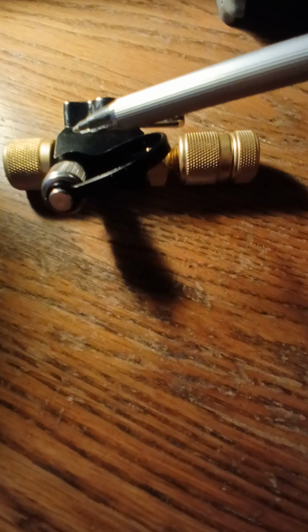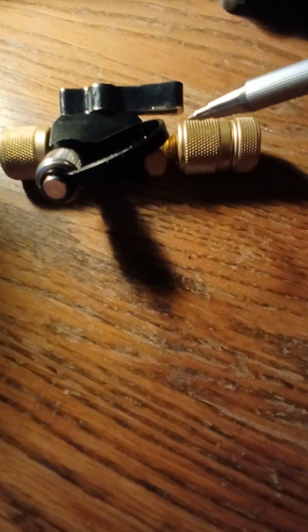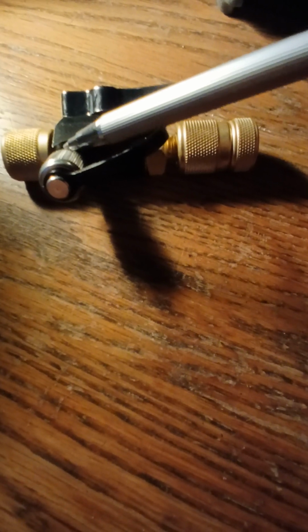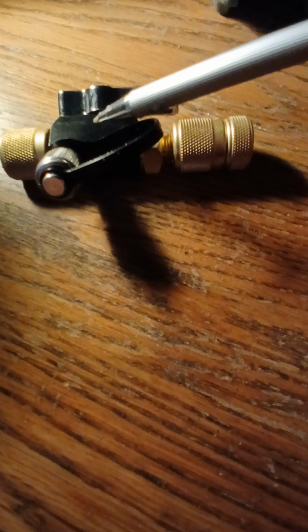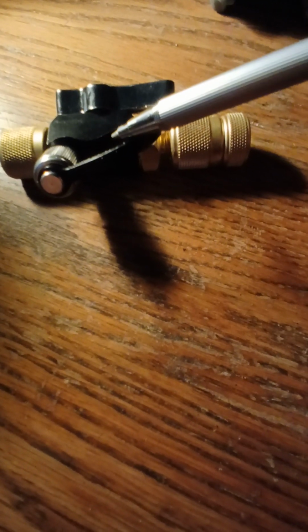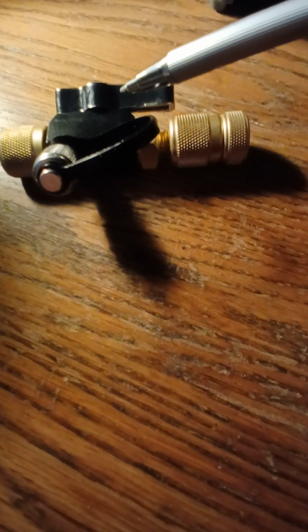My opinion is, and I hope I'm not wrong here, and again, the experts can add to this, that if you have this cutoff, you still need to build pressure so you could test your pressure here, or in a case where you were pulling a vacuum. So I'm thinking perhaps one reason that this is located in the front as opposed to on the back side is that if you cut it off on the back side, then you have no pressure, save when the handle is actually turned to the on position.